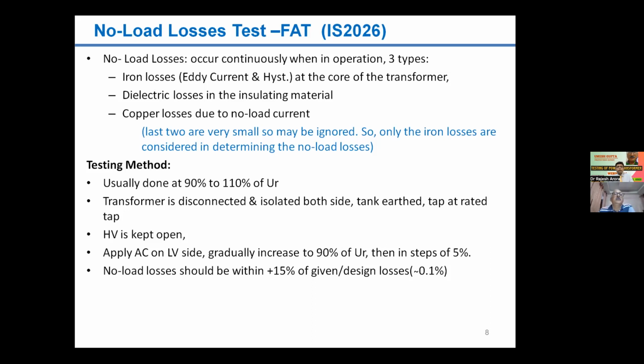So first of all, the no load losses test. It is done at the time of factory acceptance test, and is also mentioned in IS 2026, which I mentioned is like IEC 60076. Basically, what are the losses? Three types: iron losses, first of all, in the core of the transformer, then dielectric losses in the insulating material. As we know, every insulator has some component of losses. It is not purely an insulator, so some loss may occur, and because of that dielectric losses are there. And lastly, copper losses due to no load current. The last two are comparatively low in comparison to iron losses, so only iron losses are mainly considered in determining the no load losses.